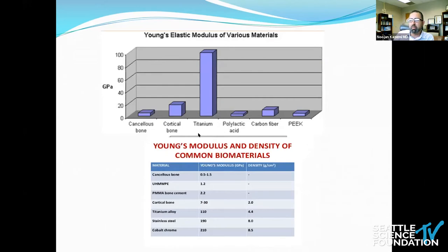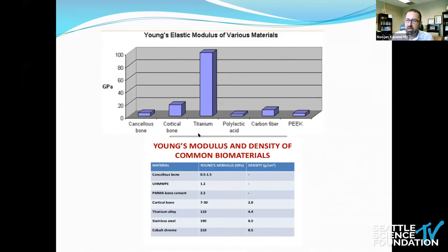The elastic modulus reflects the ability of an implant or material to deform according to the stress applied. Cancellous and cortical bone have very low elastic modulus values. Our implants — stainless steel and cobalt chrome — range from 190 to 210 GPa. There needs to be judicious selection of implants matched to our bony requirements, to achieve integration with bone but also prevent failure of either the bone or the implant. Titanium has an elastic modulus much closer to that of bone itself.